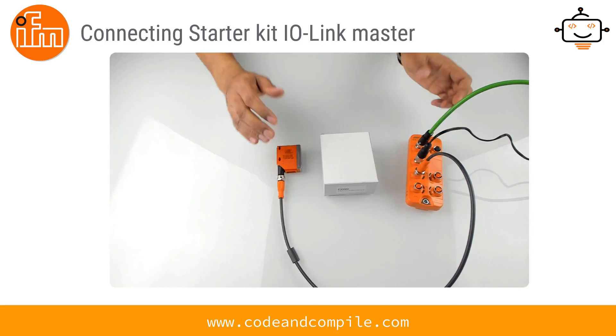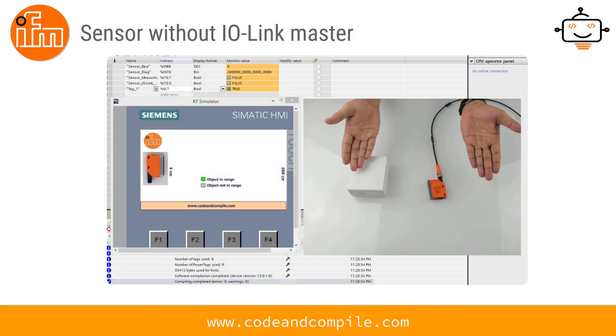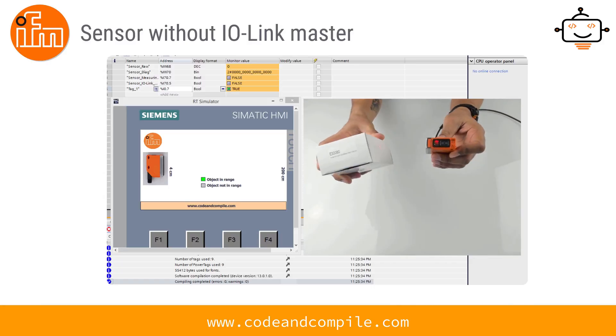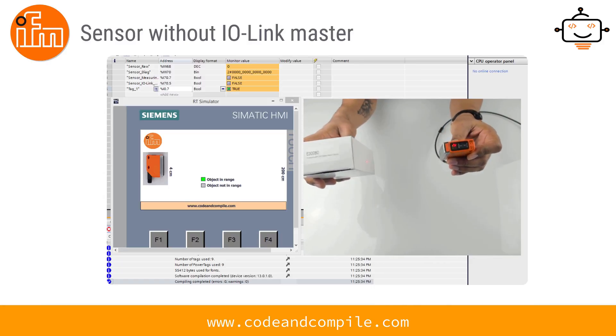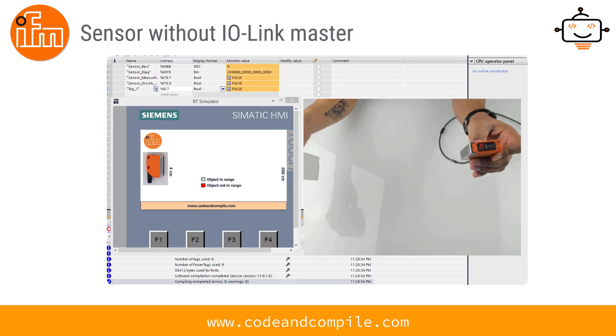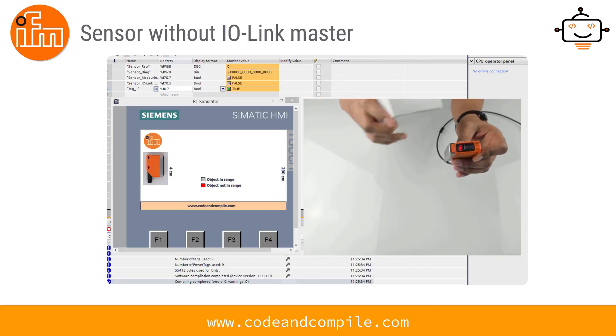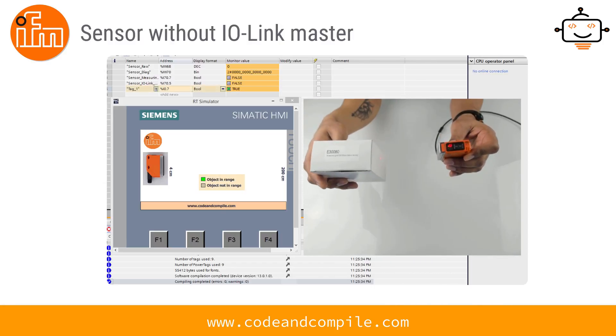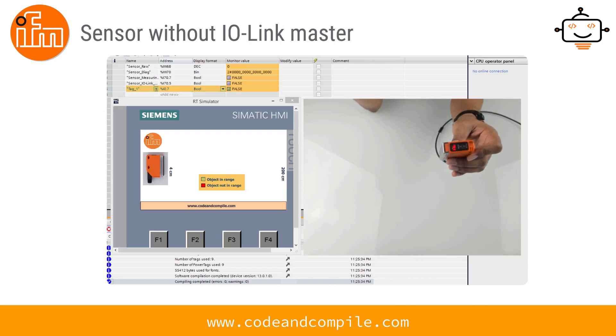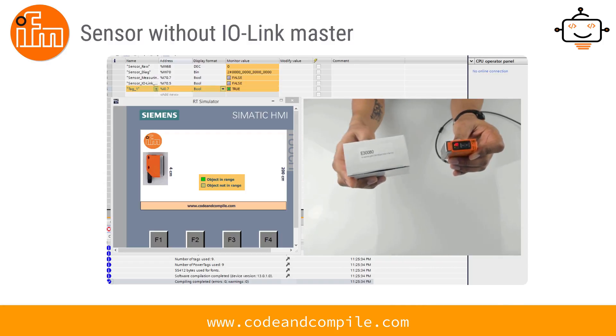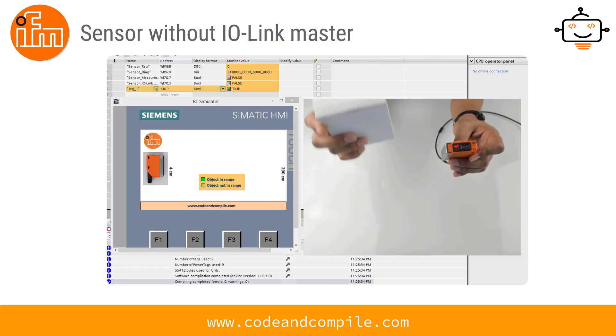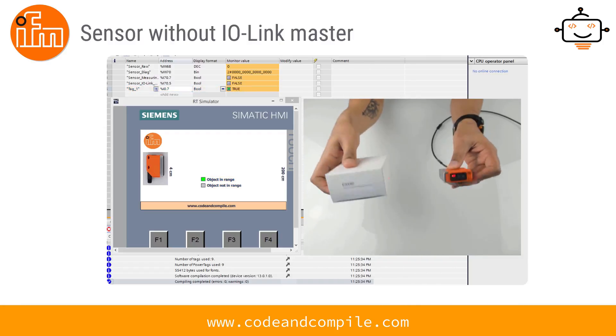We are now going to see two different ways to use the IO-Link sensor. The first way is to use the IO-Link sensor without an IO-Link master — without the AL1100 interface. In this case, the only information you get from the sensor is whether the object is present or not: when the object is present you get a high true bit, and when it is absent you don't. You simply know if the object is in range or not, and you can change the range by pressing the button on the sensor. This is the digital output from the sensor.